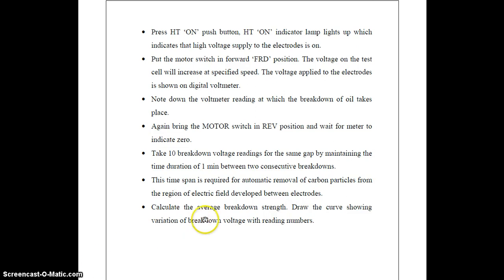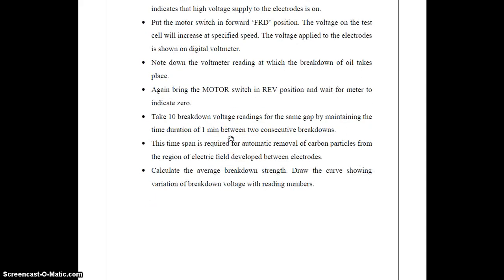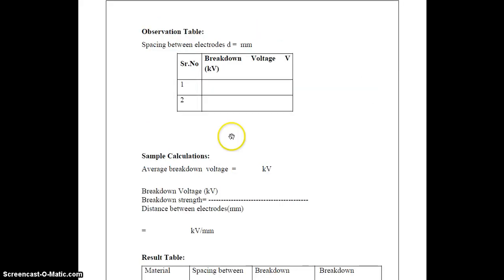Then calculate the average breakdown strength. Also draw a curve showing the variation of breakdown voltage with respect to gap distance. Then the observation table. Spacing between electrodes is D mm. Then breakdown voltage in kilovolt. Then the sample calculation: obtain and calculate the average breakdown voltage in kilovolt.